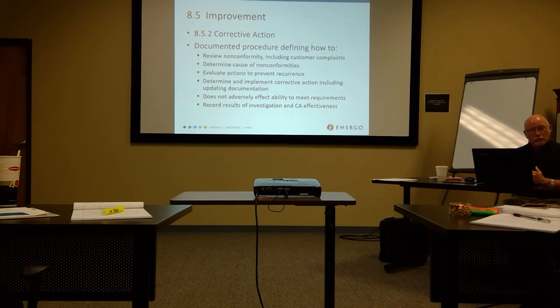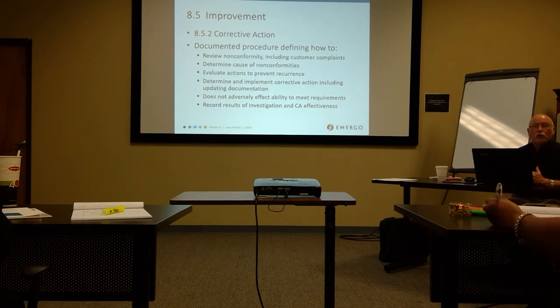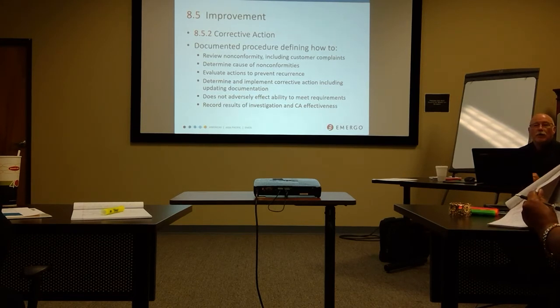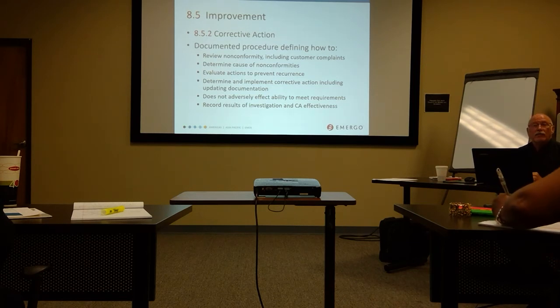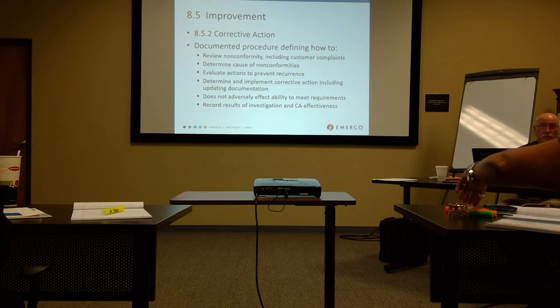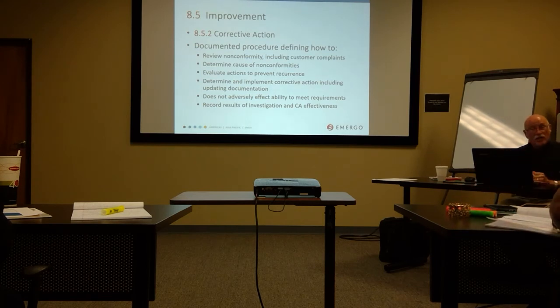CAPA, like complaint, has to be very carefully managed. So let's take an audit nonconformance. That's probably the easiest one to follow. So if you're cited in an internal audit, external audit, whichever, you actually get a nonconformance. So the expectation is for any audit nonconformance that generates CAPA. OFIs are at your discretion. OFIs, opportunities for improvement, are great opportunities for the preventative side of CAPA. It's not a requirement, won't be cited if you don't do it, but it's an opportunity that I would recommend you take advantage of. Nonconformances, you've screwed up, you're out of compliance, that's guaranteed CAPA.